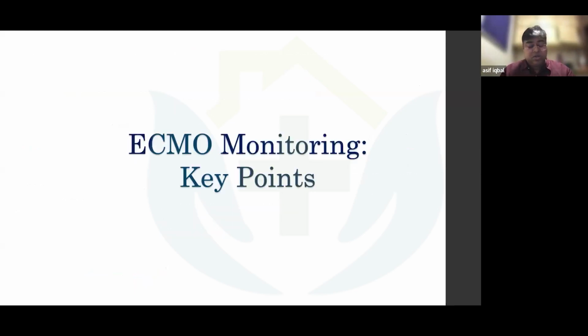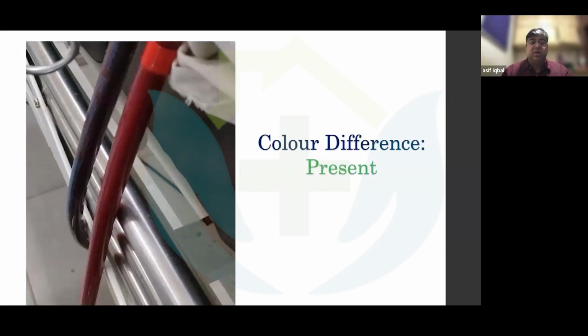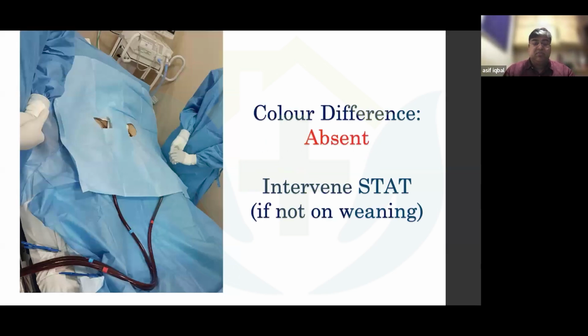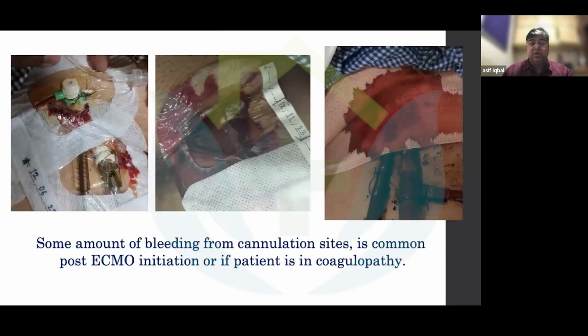And ECMO monitoring is very important. These are the troubleshooting questions you will face in ECMO. One is color changes. The first thing in monitoring is to watch the color. The drainage cannula always has black desaturated blood, and the return cannula will always be bright red. Then everything is perfect. If both cannulas are black, your oxygenator life has gone, so you have to change the oxygenator. If both cannulas are bright red, then recirculation is happening, so you have to check the position of your cannula.